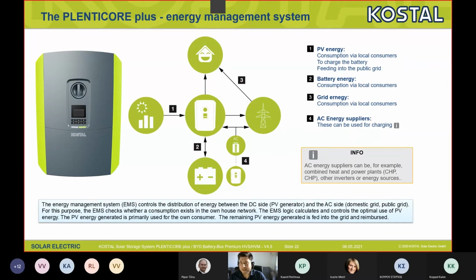Also, I have to mention that in case we have a power off from the grid provider, the inverter will switch off because the inverter could not work. We need an external backup solution, which actually is not available right now. The system has been designed according to the self-consumption scheme.